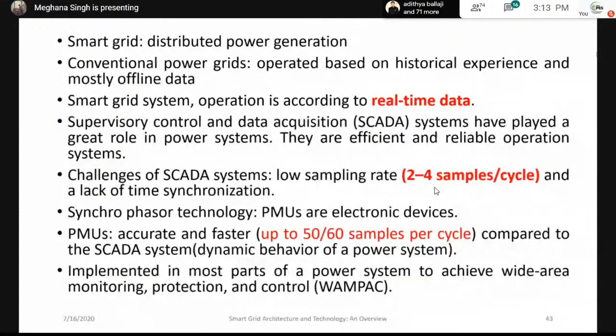You have a phase lock oscillator, which is used for time tagging, that is for sending out the phasors within the second. Time tags are added to the analog voltage and current signals, which are passed through a filter and an A to D converter. Then it is sent to the microprocessor, which computes the voltage and current phasors, frequency and ROCOF, the rate of change of frequency, and binary information. These data are then sent within frames to phasor data concentrators. So you have the time tag, then the data from the microprocessor, which is given to the PDCs, and the PDCs will use that data.